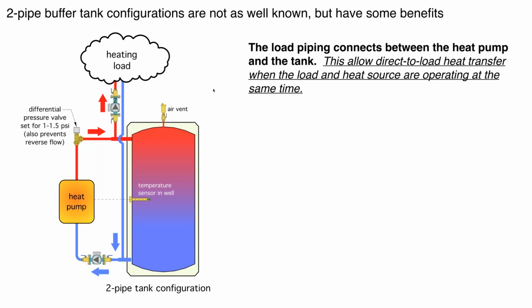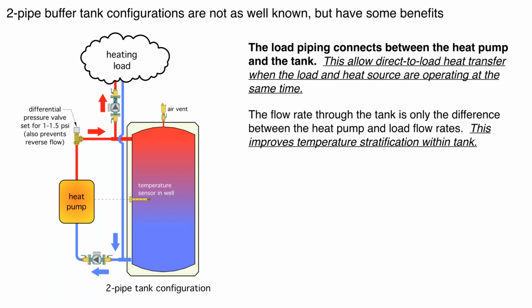Now, in a two-pipe configuration, I mentioned this direct-to-load concept, all right? And what the difference is, you can see, instead of taking the load circuit off over here on the right, we're taking the load off just upstream of the buffer tank. So we can intercept this water coming up through here and send it out through there. So we do have the advantage that if the tank was cool, we could get warmer water to the load faster with this configuration. I also mentioned that when the load and the heat pump are operating simultaneously, the only flow that is going through the buffer tank is the difference.